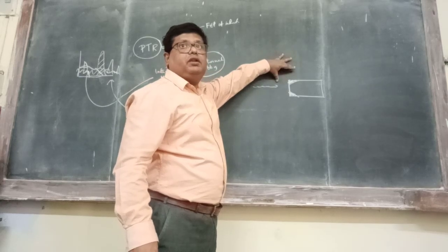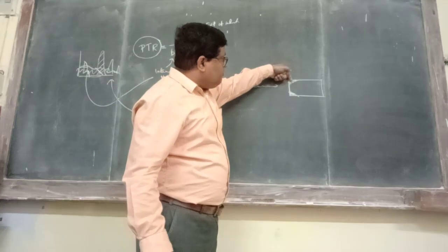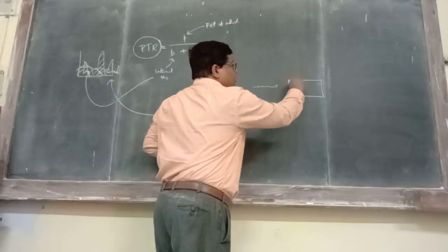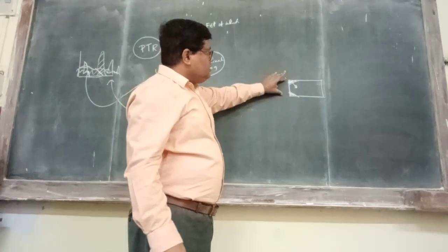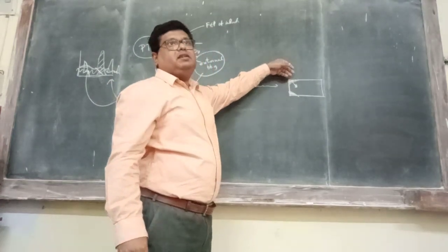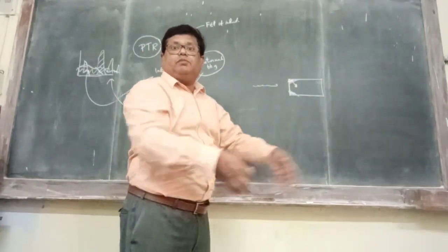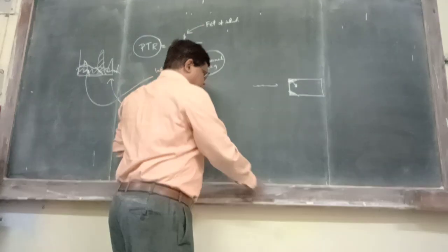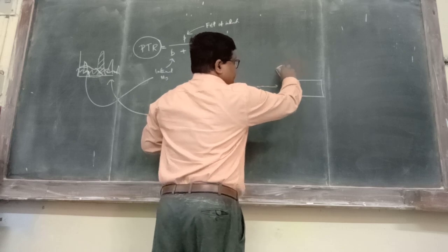That means we will lose the gamma ray, and there is very little chance that the scattered gamma ray after scattering from this part will enter the detector. Because this part is basically dead weight. If we keep this, we are basically inviting more Compton scattered gamma rays. So we will get rid of this. And this first technique is known as tapering.